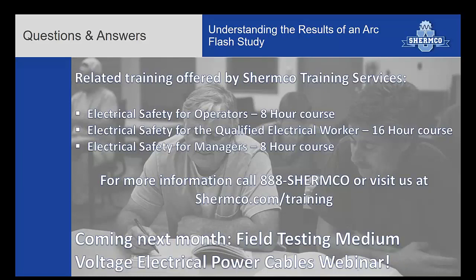Let's see. Another one that came in is when equipment can be fed from multiple sources, say a load downstream of an automatic transfer switch, the values can be much different depending if it is on generator or on utility. Which source should we be using for the arc flash label?